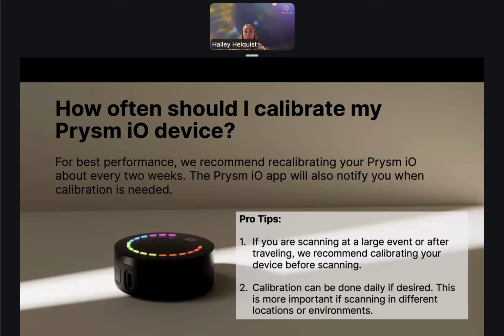We know shifts in temperature, or moving the device around a lot, can have an effect. Again, if it's at the bottom of a bag and getting knocked around a little bit, that can impact its calibration. And so best practice is always to make sure that the device is stored in its travel case if possible. And then if you do happen to leave it in the car, or bring it into a warmer environment or a colder environment, calibration is most likely going to be needed.